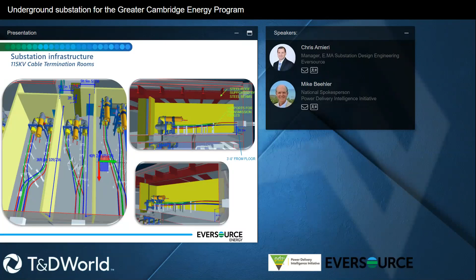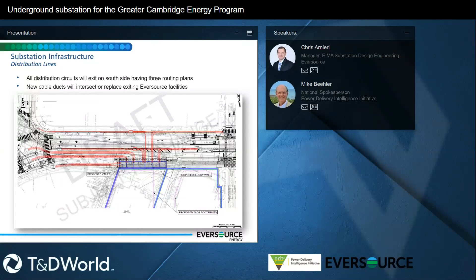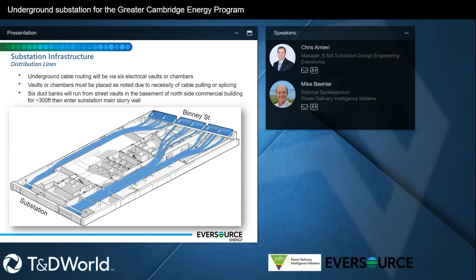First thing we did, coming from the north side, you can see in red the distribution circuits. We transitioned them into the closest point to the commercial building and put pulling vaults into that space. Since the commercial building had a below grade parking garage, we had to heavily work with the partner to figure out how to route distribution duct banks on the top ceiling of the topmost garage level. As you can see in this image, there's a lot going on between ramps, passages, and clearances for cars, but we also needed to keep the thermal ratings down on the distribution duct banks to supply the appropriate amount of load.